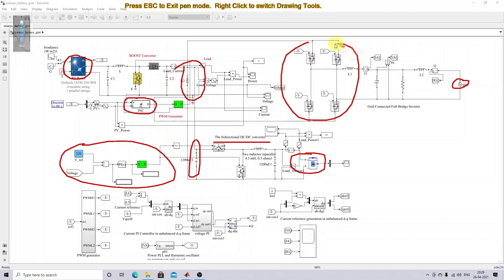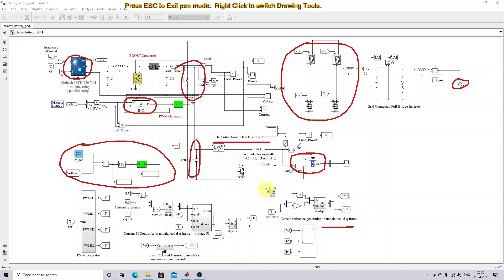This DC bus is connected with a voltage converter and the grid. This is the grid, and this is a full-bridge voltage inverter. This inverter is controlled by means of DQ frame control — here we generate the reference current: D-reference and Q-reference.